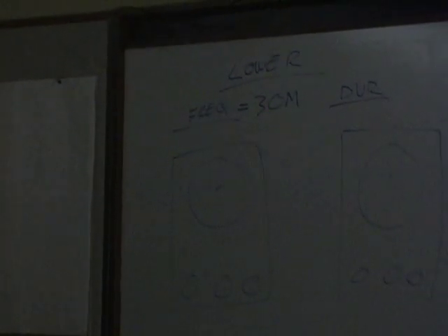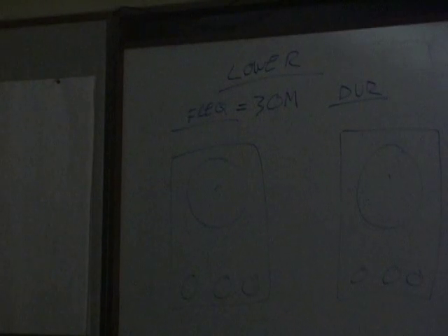For the lower, the reason why I bumped that one back to 28 minutes is because it's only a 90-second, or 1.5 minute, cycle. That cycle will be over when this one kicks in right on the even half hour, which I set it at. So we want our frequency for this lower one to equal 30 minutes, or right on the half hour. So it's going to do 2 times exactly every hour.